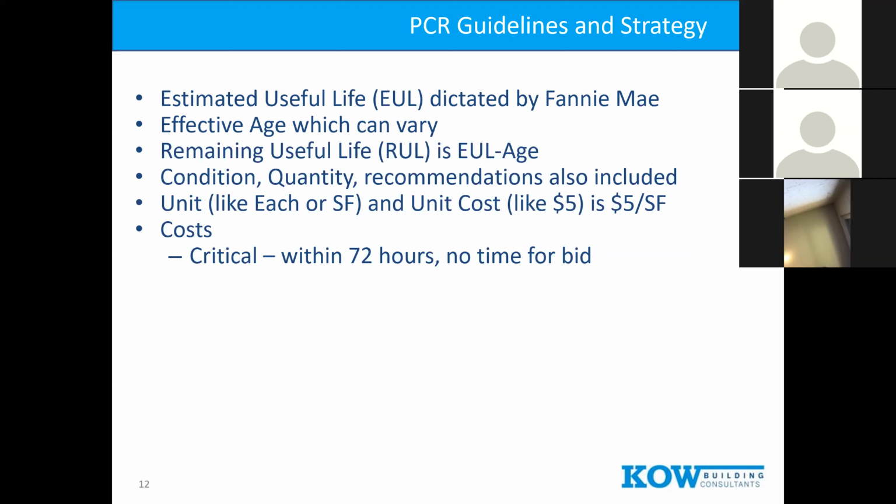That's not going to work. You need better attention to that. Even if you just put up a temporary structure with something to divert the water away, that's not going to keep water away because it's just destined to fail. That's a critical. They're fairly rare, but we reserve it for something you have to put attention to immediately.